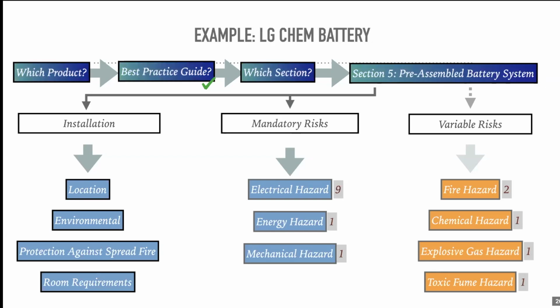So for instance, the fire hazard is determined somewhat by location as well. If you go to a battery system that you are connecting to your own installed PCE inverter or charge controller, an example would be an LG Chem battery. It's a pre-assembled battery system, and by that it means it's got its own battery management system. It has its own integral safety systems built into it to protect it. BYD, for instance, would also be in this category. It's got a few more requirements in terms of electrical hazards because of the requirement for cabling, and a similar amount of fire and chemical and explosive hazards. So really sections 4 and 5 aren't tremendously different. Mostly it's about the electrical connections and protection of the DC cables.